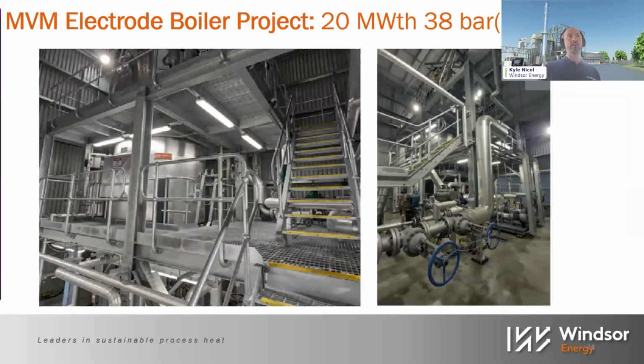The success factors were that this was the first fully electrified dairy plant in New Zealand. It proved that a large-scale, high-pressure electrode boiler would work. It provided a significant emission reduction of 22,000 tonnes a year, and there was successful delivery, integration, and commissioning with minimal operational disruption.